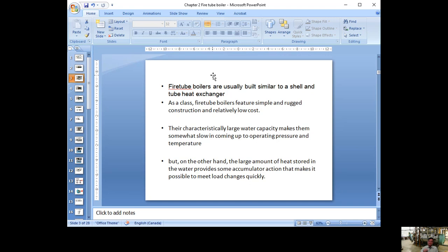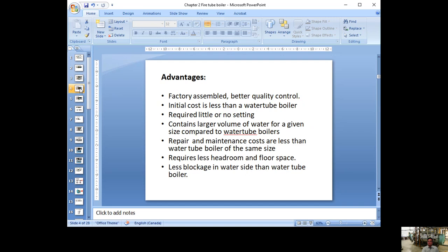If you don't have much water — like in a water tube boiler — when someone turns on equipment and demands steam, you have to use a water pump to pump cold water inside the boiler, heat it up, and then make steam, which takes a bit longer. So the fire tube boiler can handle load fluctuations a little bit better than the water tube boiler.